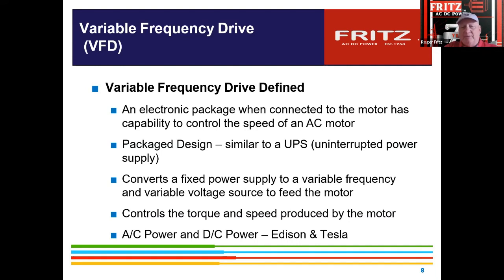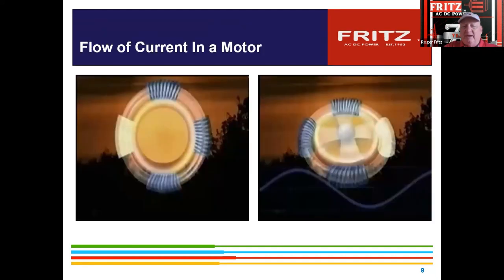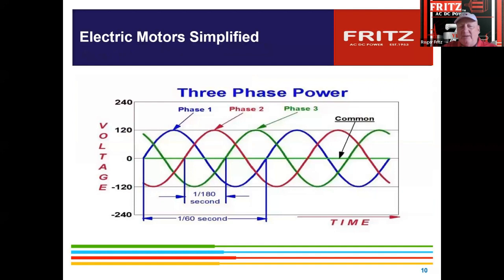AC power and DC power, the difference between them: Edison was a DC guy and Tesla was the AC guy, and Tesla's the one that won out for Niagara Falls. So again, you've got these rotating fields that were shown in the video, and because of the sine wave, they will trigger when the north and south pole functions on that coil. From that, as we speed up and slow down this frequency and voltage amplitude, we're able to control that AC motor, which before was not able to be done. And that's the nuts and bolts of what we're doing. But then when you do that, you get the advantage.